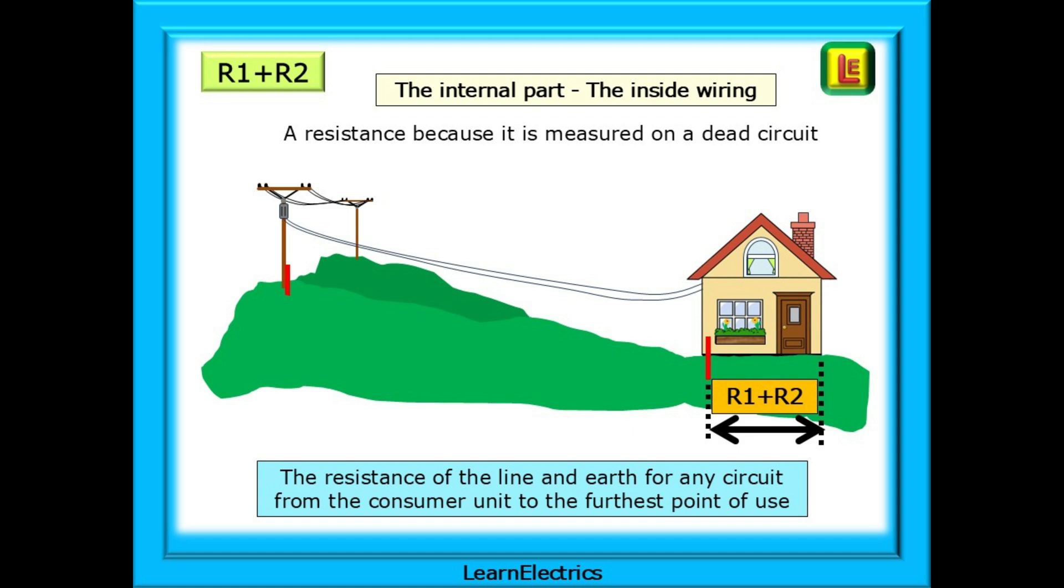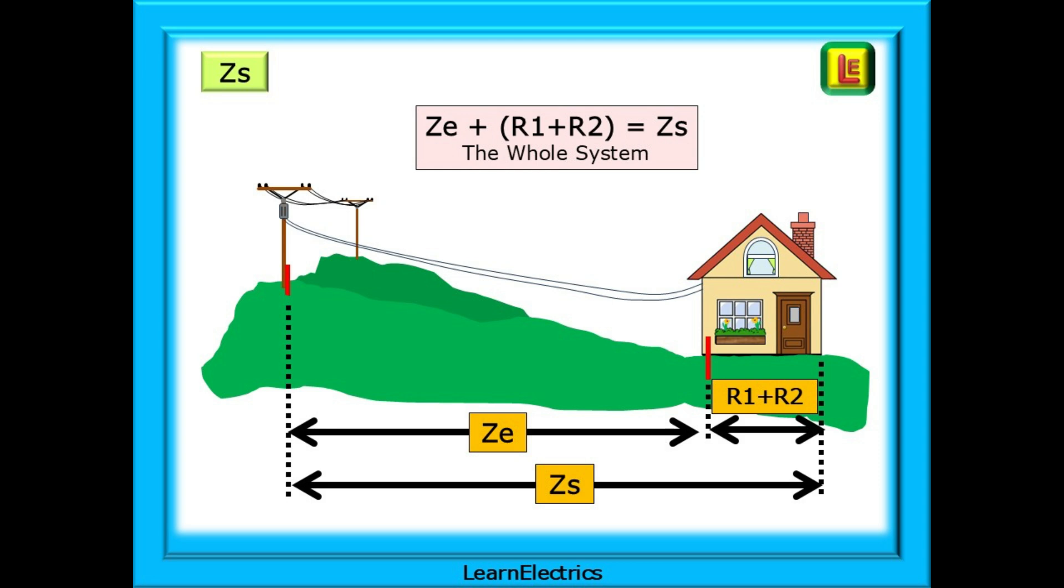R1 plus R2 is the internal wiring of the property, the inside wiring. We call this a resistance measured in ohms because it is measured on a dead circuit. It is the resistance of the line and earth for any circuit from the consumer unit to the furthest point of use in the house and back to the consumer unit. The lights will have an R1 plus R2, an immersion heater will have its own R1 plus R2, and so will the sockets. The whole thing, the whole wiring system, inside and outside, is called ZS, and it is made up of two parts.